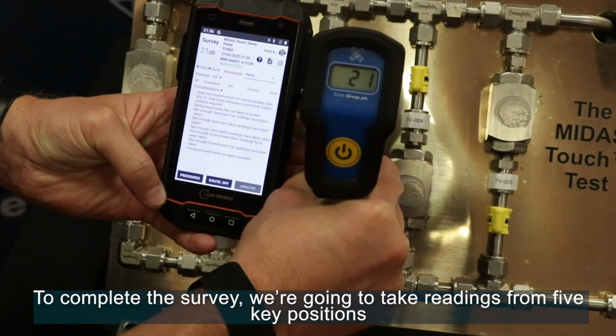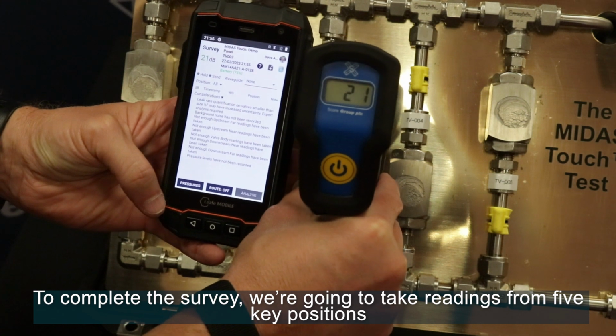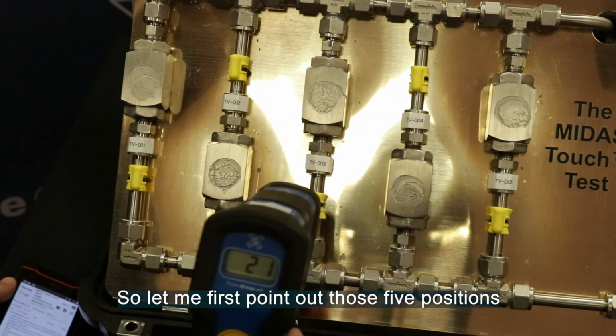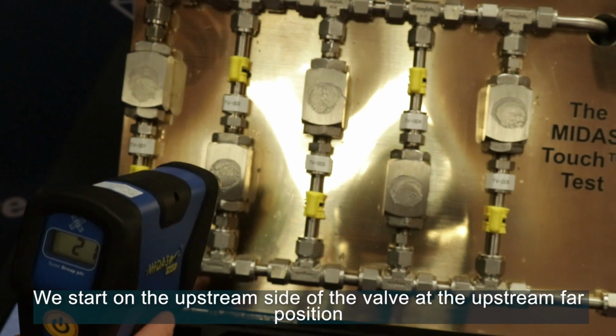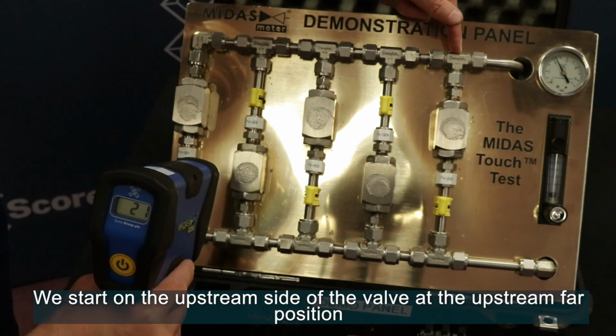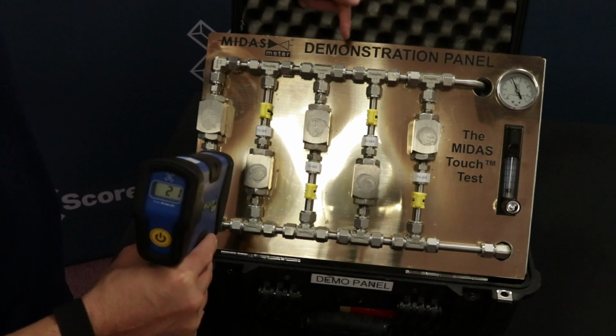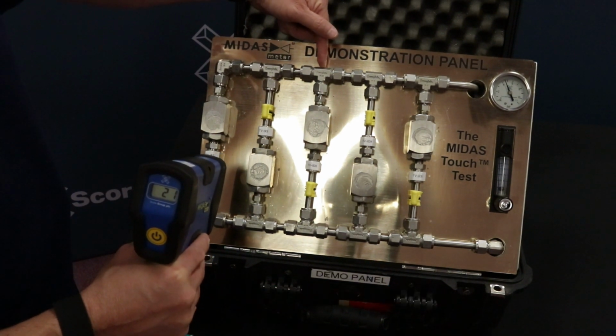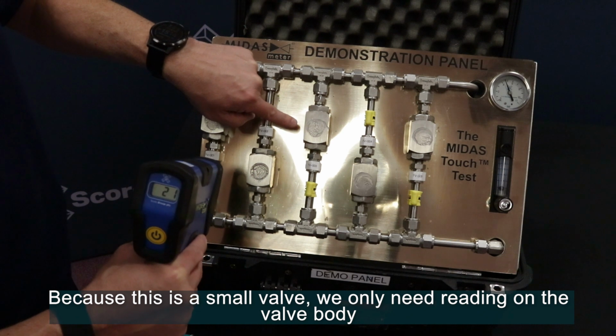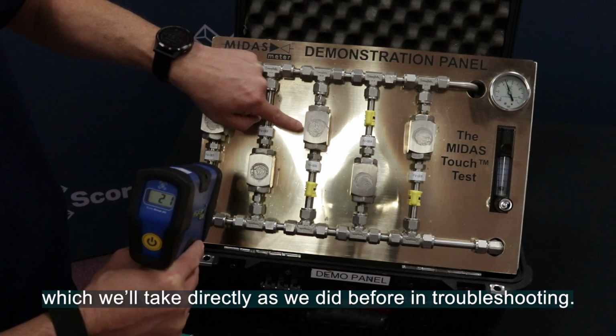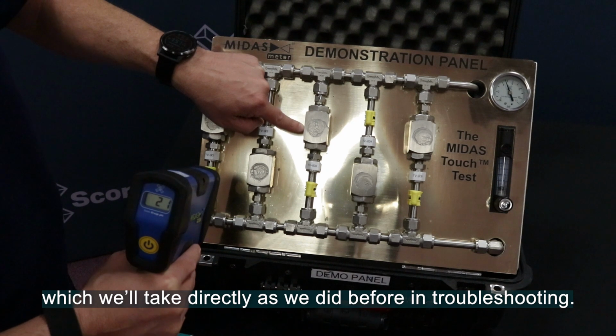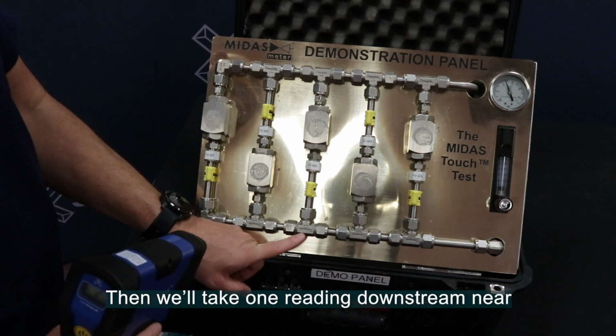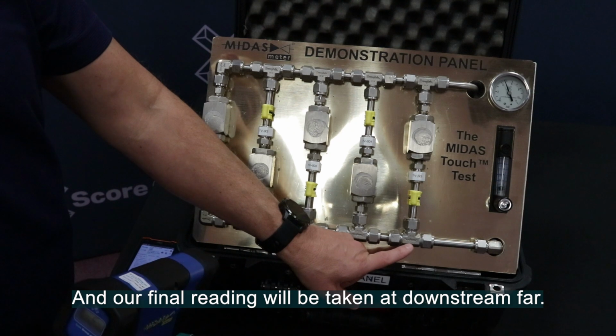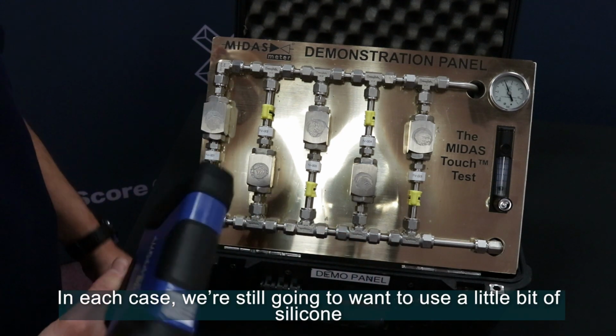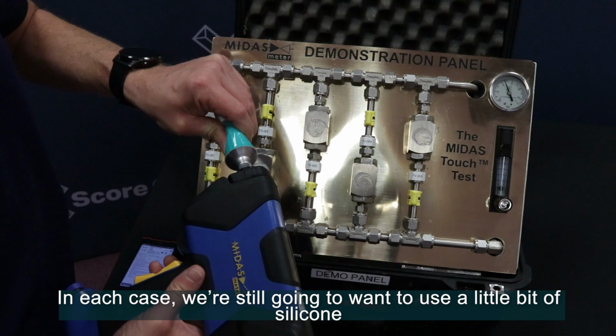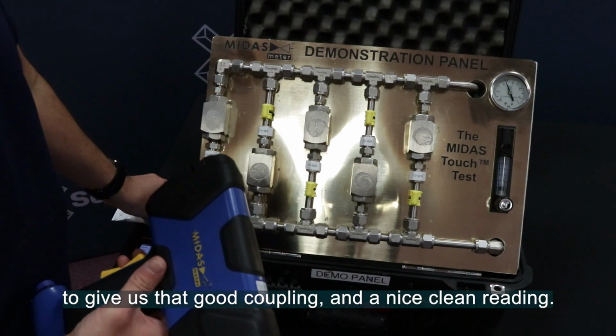To complete the survey, we're going to take readings at 5 key positions. So let me first point out those 5 positions. We start on the upstream side of the valve at the upstream far position. We then move to upstream near. Because this is a small valve, we only need 1 reading on the valve body, which we'll take directly as we did before in troubleshooting. Then we'll take 1 reading downstream near, and our final reading will be taken at downstream far. In each case, we're still going to want to use a little bit of silicone to give us that good coupling and a nice clean reading.